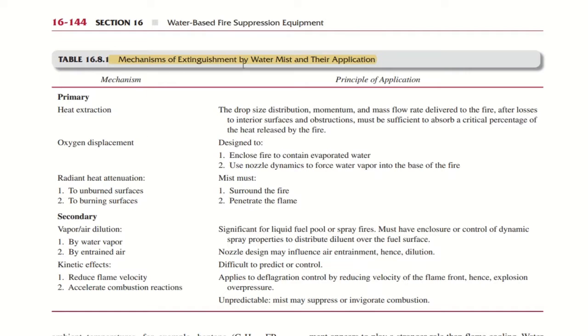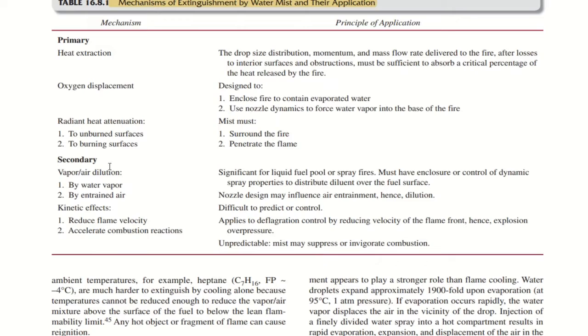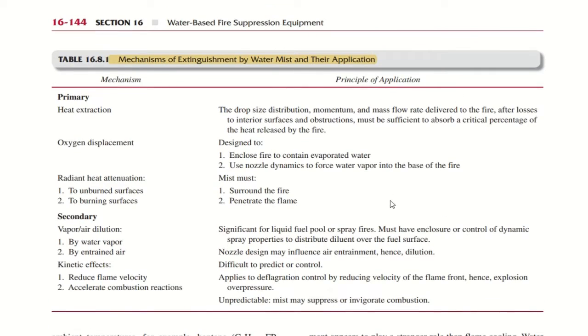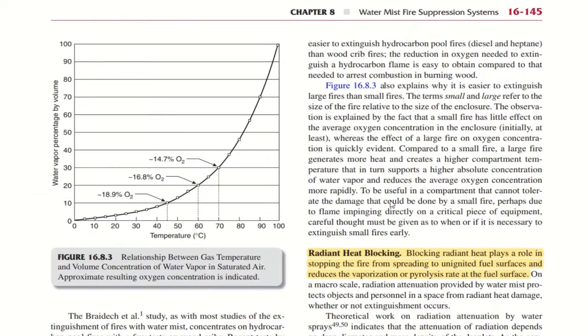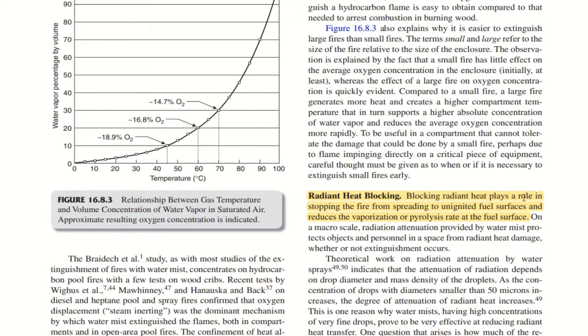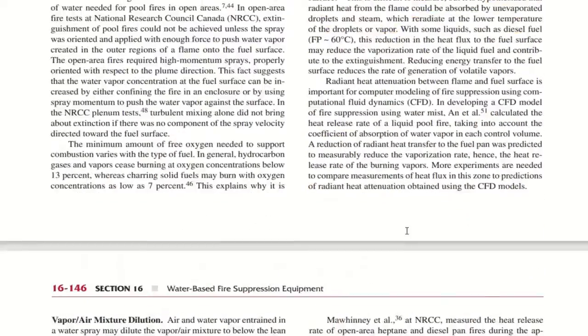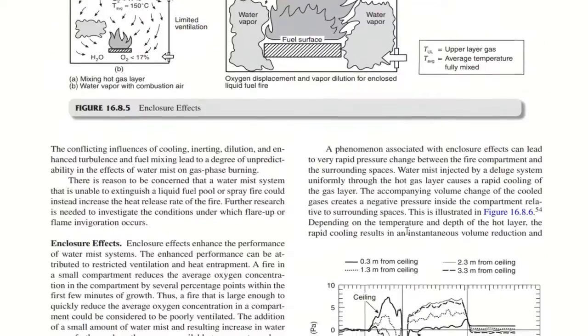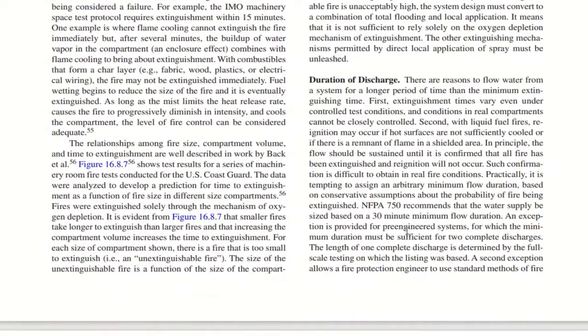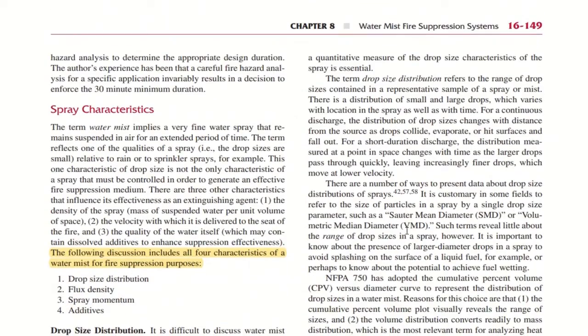You just go through the mechanism of extinguishment by water mist and their application. Here you have primary and secondary mechanisms. Just go through the principle of application. Here you have radiant heat blocking. Blocking radiant heat plays a role in stopping the fire from spreading to unignited fuel surfaces and reduces the vaporization or pyrolysis rate at the fuel surface. So there are so many things to be discussed. Since time does not permit, I am ignoring some of the points and covering only the major portion, the most important points which are helpful for your examinations.